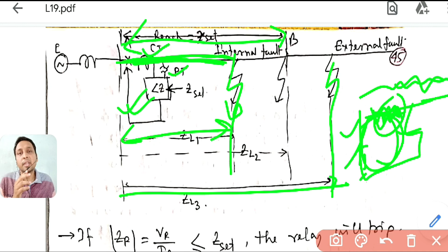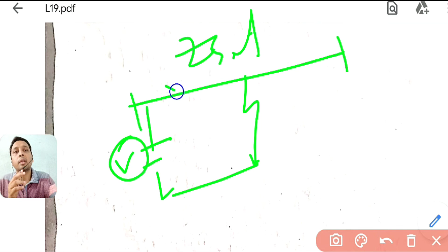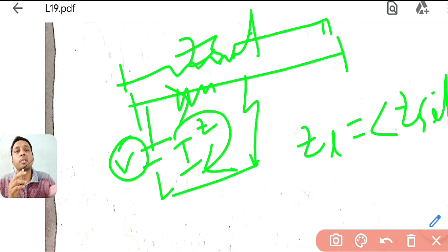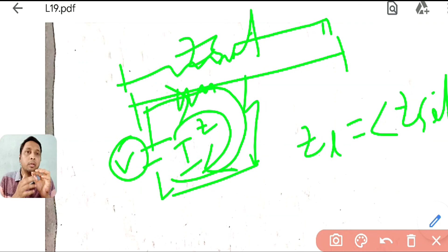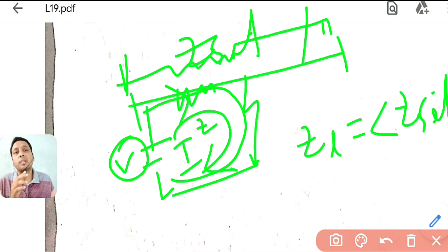Let me draw it one more time here. Suppose the fault is now here, this was the section. This is my Z set value. Now the fault is here, so you are sensing voltage and current from here. So what will be my Z? This will be my Z, ZL. But what was the actual Z? The actual Z was from here to here. So if you are doing the KVL here, your ZL will obviously be less than your Z set, because it is not taking the full path, it is taking only this much path. So your Z that is calculated by the relay will be less than your Z set. So hence it will trip. So now you got it. This is the idea of how your distance protection works.